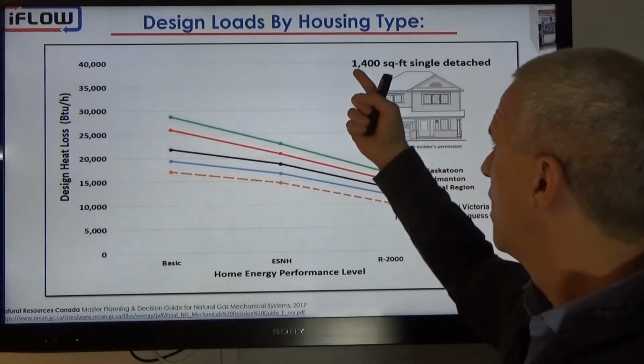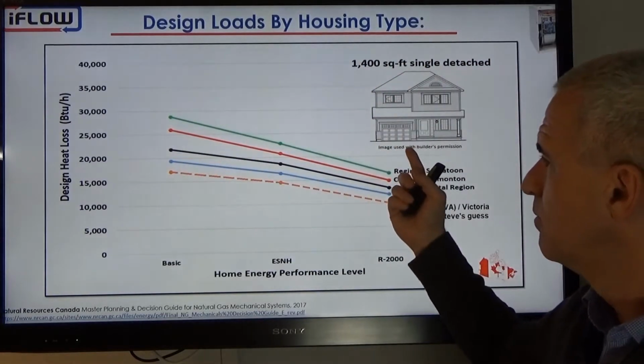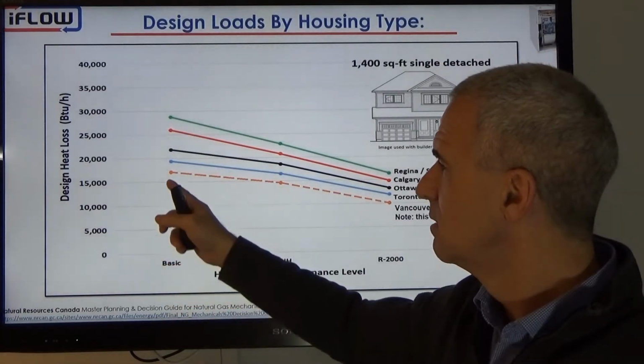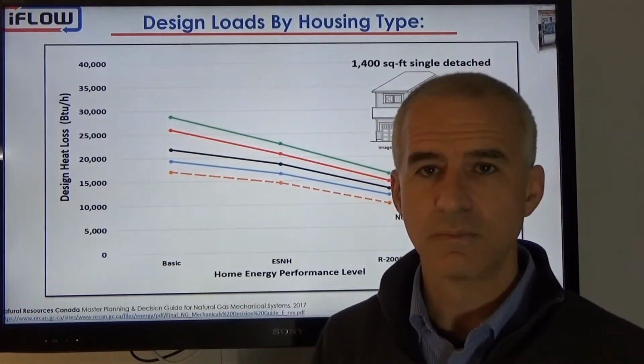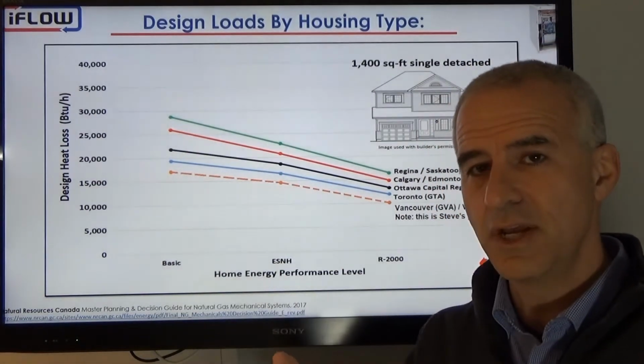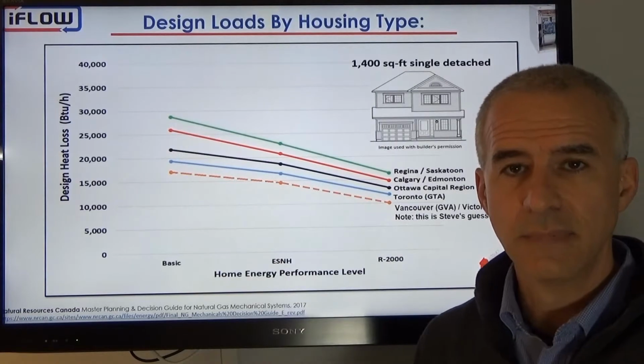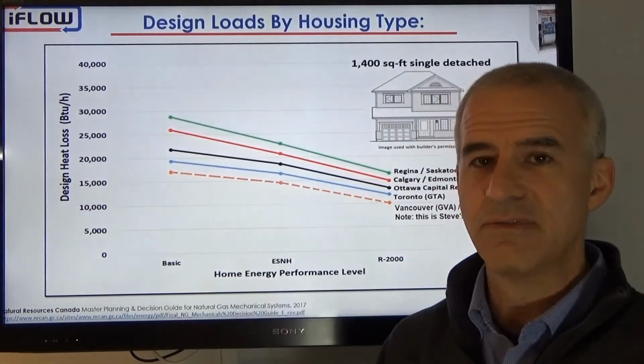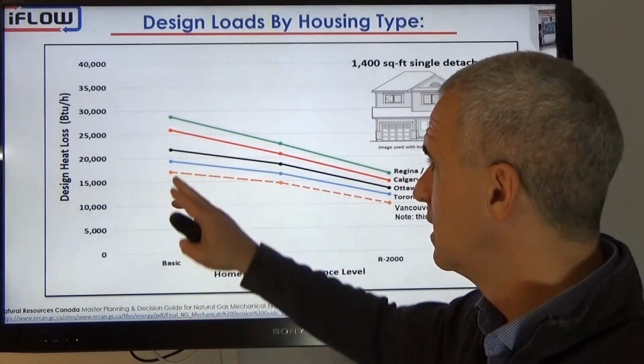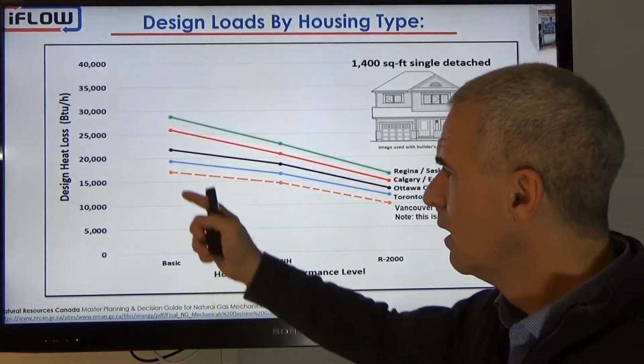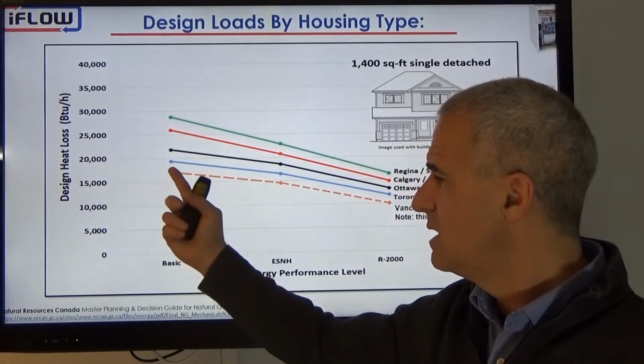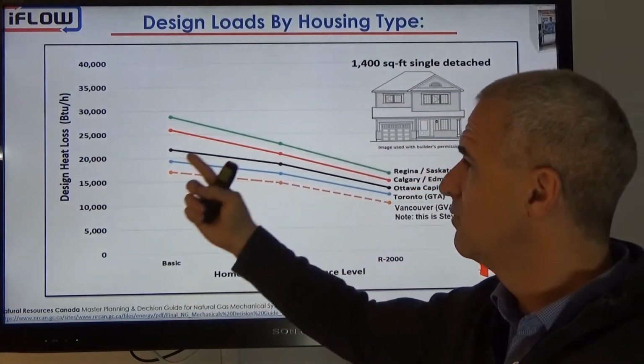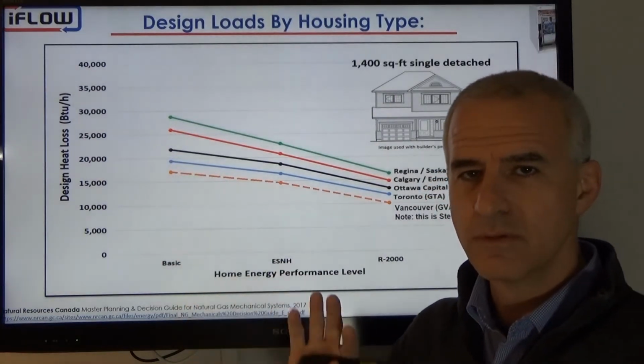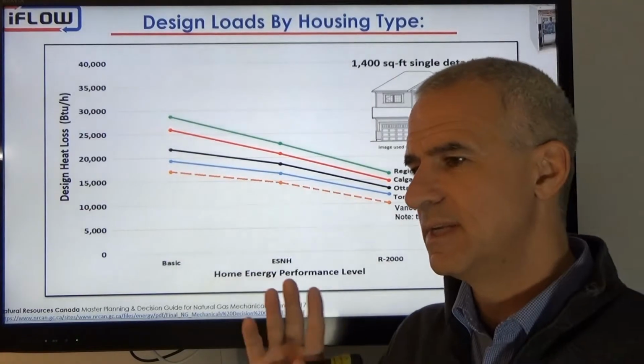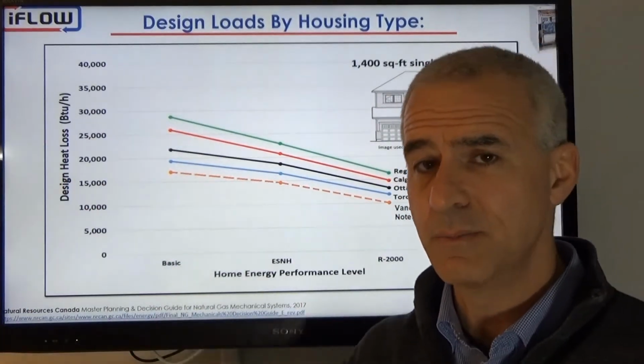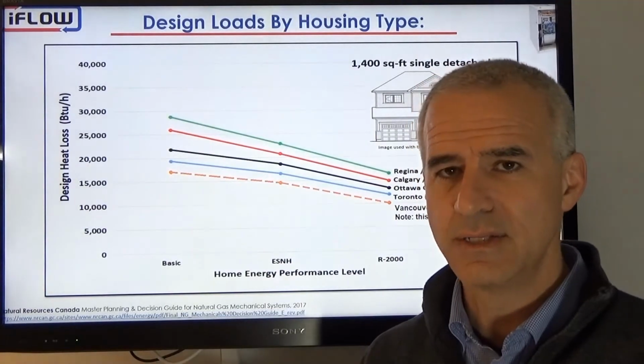And you see that for a 1,400 square foot single detached home, on basic standard construction, heat loads are less than 30,000 BTUs. And that's on the worst day in January in one of the coldest cities in Canada. So you can see that if you are south of that, it's going to be even lower than that 30,000 BTU. And as you go into Toronto, for example, we see that even on standard building code for a 1,400 square foot single detached, less than 20,000 BTUs. Those are very, very low heat loads. And you know, the days of putting in a 100,000 BTU furnace or an 80,000 BTU furnace, those are long gone. We're way oversizing if we're doing that.